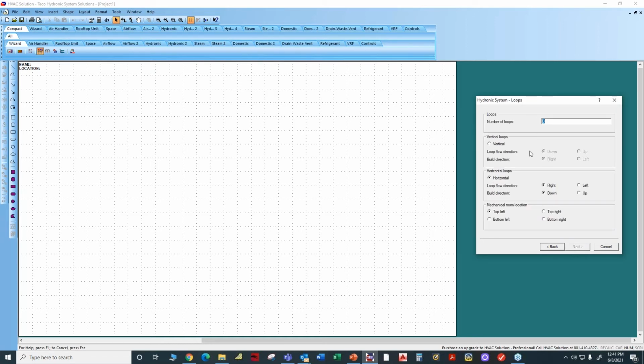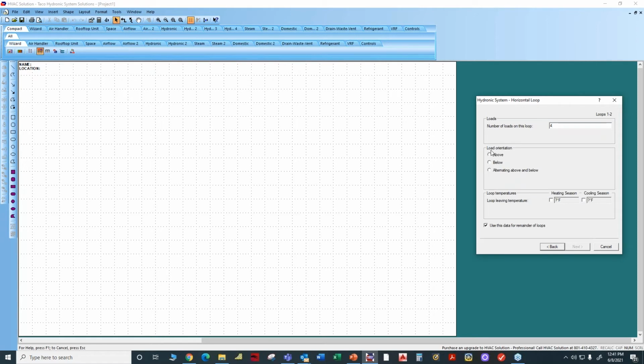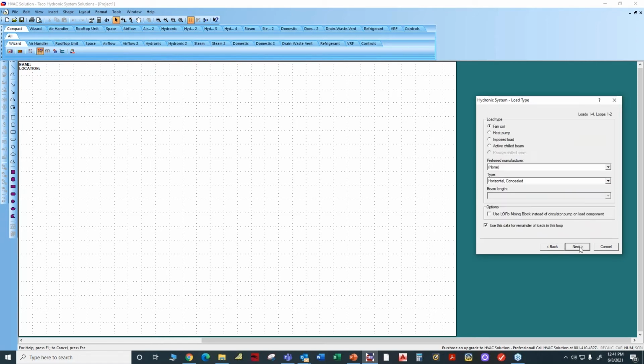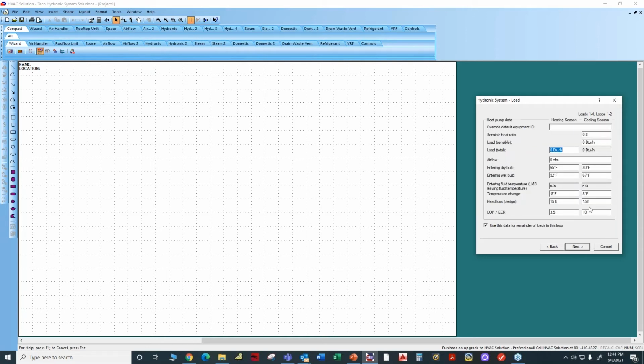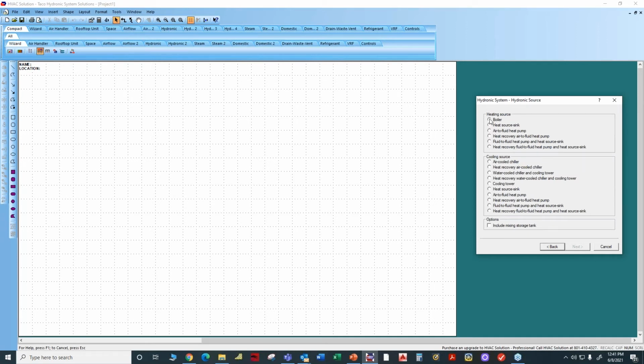Again, similar to before, I'm just going to have 2 loops, and I'm going to have 4 terminal devices per loop. We'll put the load orientation above. And in this case, it's going to be a heat pump. And we're going to put in here 48,000 BTUs per hour for the cooling, and the same thing for the heating, just for the fun of it, keep it the same. Oops, sorry, we'll put in 60,000 for the heating. And then the heat source will be a boiler, and the cooling source will be a cooling tower. And in a minute, we're going to talk a little bit about the cooling tower.